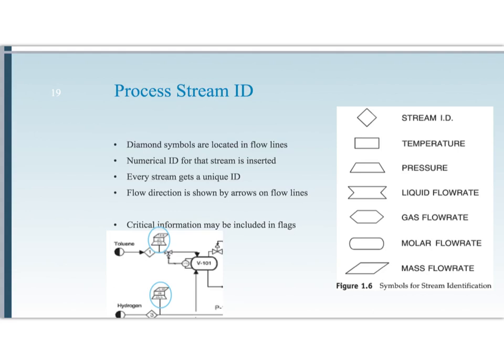For really critical process conditions, we want to identify those on the flow lines in the most compact way possible. A lot of times this is done using flags — each different piece of information has a different shape. A temperature is a rectangle, pressure is a trapezoid, and so forth. You stack them on top of each other for whichever ones you need. So if it's really important that you get the temperature right or the flow rate right, then you indicate those using these flags.